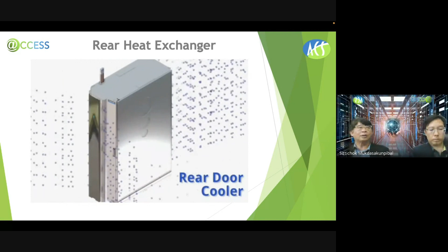Rear door exchanger, there's another one. In the market we are talking about 55 kilowatt to 200 kilowatts, that's what I have seen so far. So this is how it works: the exchanger will basically draw in all the hot air of the server, and of course it's still considered liquid over here at the door side. You can put it into a system of different racks together, and then hook it up to your local chiller, so your water chiller will still be working.